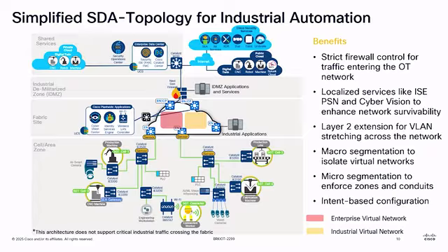There are some industries that need to have completely separated IT and OT. But we have seen this as an appealing case coming up. So we have the logical separation enabled by SD access. And the communication between these networks is policed by the firewall on the top, which is the peer device in this case. We can add multiple virtual networks. On top of that, we can have a building management system. We can have a virtual network for IDMZ, so there are some jump hosts to access applications. We can have many of these, what we call overlays in SD access, that are completely isolated from each other.